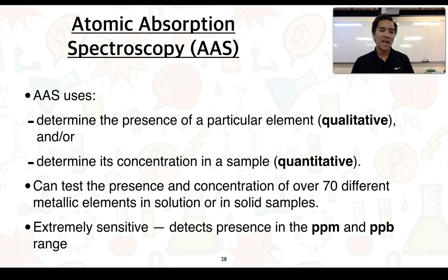Atomic absorption spectroscopy or AAS for short can be used to determine the presence of a particular element which we can think of as qualitative analysis and or determine its concentration in a sample which is a quantitative analysis. It can test the presence and concentration of over 70 different metallic elements in solution or in solid samples. It is extremely sensitive, it can detect the presence in the parts per million and parts per billion ranges.